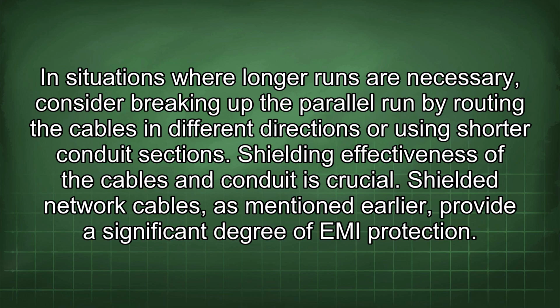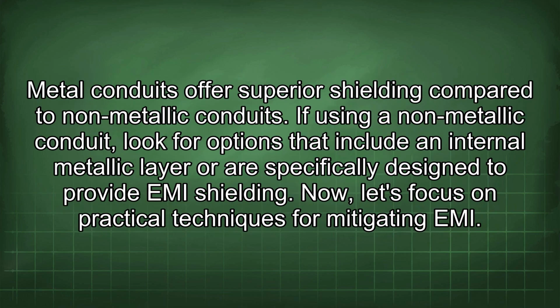Shielding effectiveness of the cables and conduit is crucial. Shielded network cables, as mentioned earlier, provide a significant degree of EMI protection. Metal conduits offer superior shielding compared to non-metallic conduits. If using a non-metallic conduit, look for options that include an internal metallic layer or are specifically designed to provide EMI shielding. Now let's focus on practical techniques for mitigating EMI.